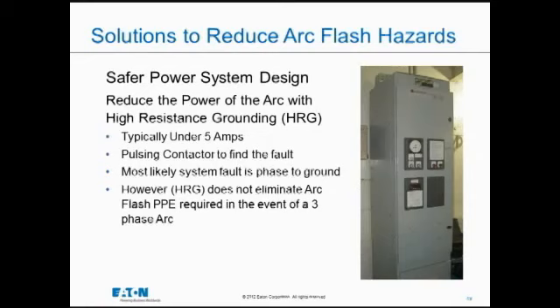For those of you that are doing power system designs, this one certainly makes a lot of sense for arc flash. Why do we want a very strong short circuit current for a phase to ground fault if we don't need solid grounding? And so rather than solidly grounding the main power transformer and distributing a 4th wire in our system, reduce that exposure for a line to ground fault that's high short circuit current, reduce that only to those places where we need the 4th wire. So when we have single phase loads, or let's say 347 volt lighting, we would put a smaller transformer in that location, solidly ground the neutral, run a 4th wire, and that system does have high short circuit currents.